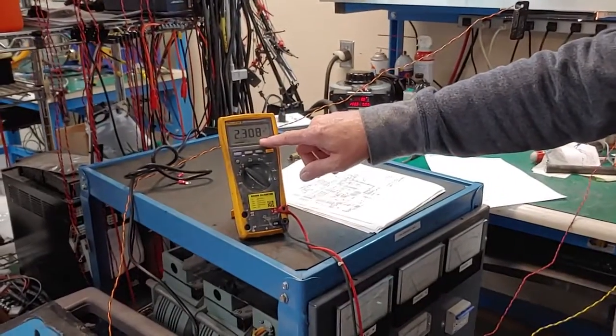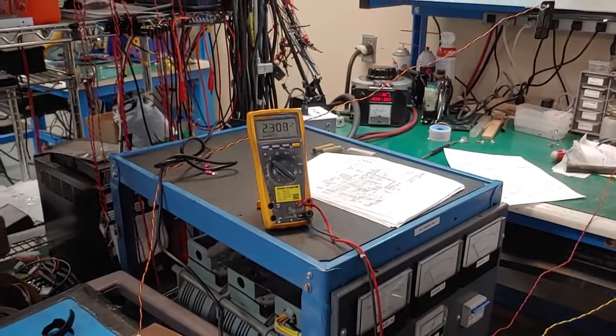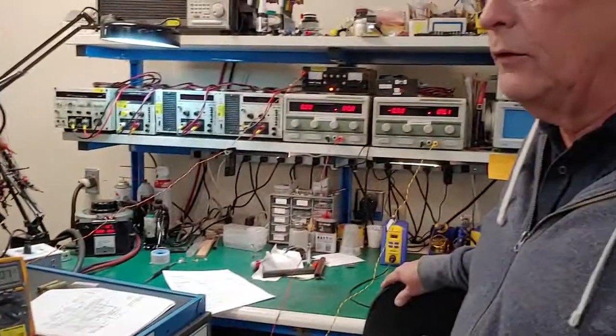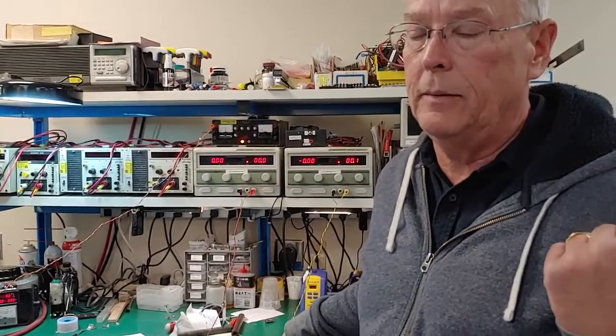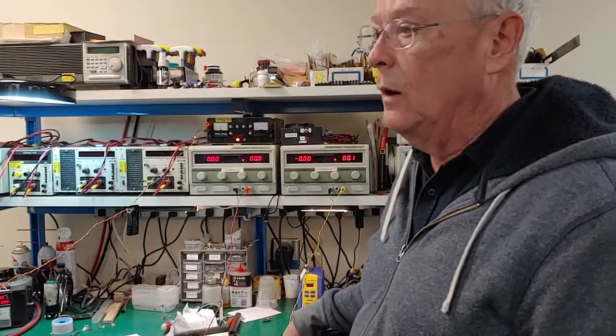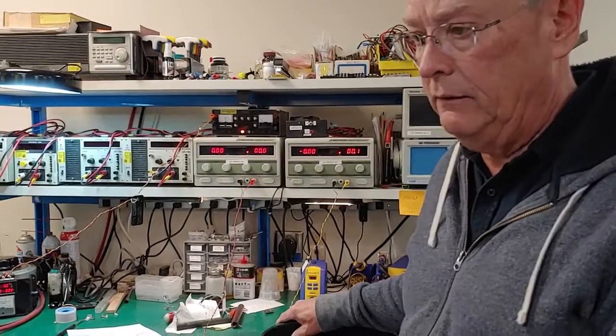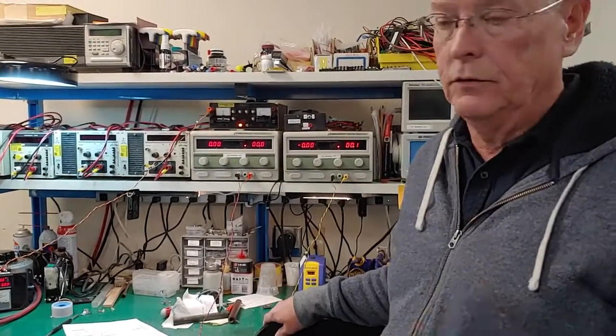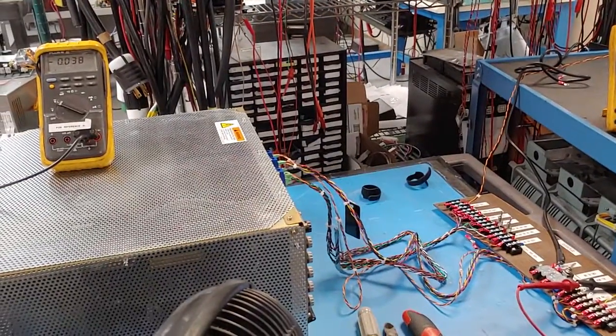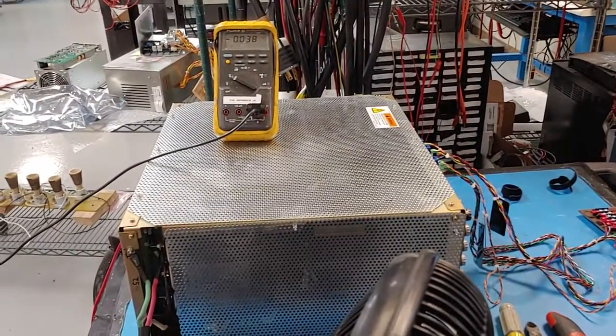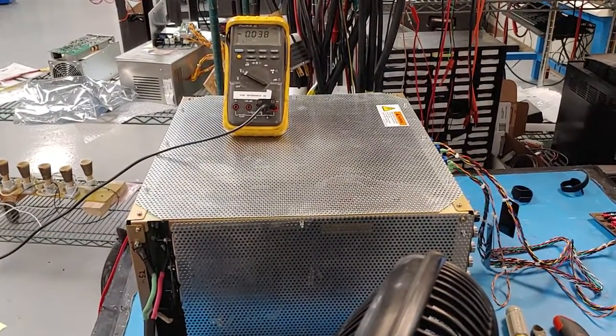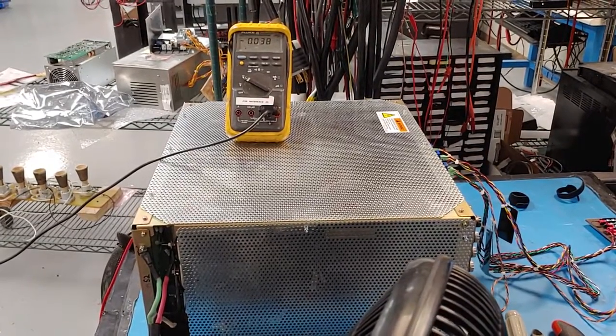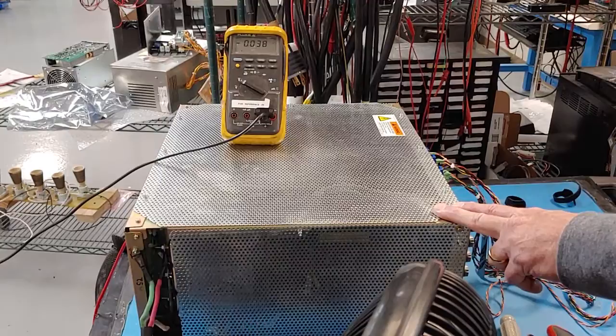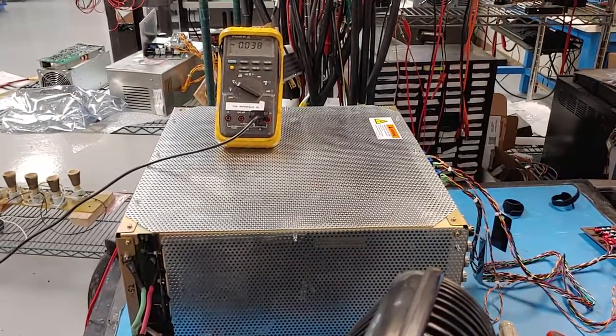We've got filaments now at 2.3. This is a standby filament. It allows them to warm up on this one without the high voltage being up. Like I said, the other one's different. The high voltage has to be up to about 15,000 before the filaments will come up. So it's by circuit design. Even though they're the same number, there's 2 different versions of circuits. So this one, by the way, is the one that was in your inventory as a spare, and we sent back fully repaired last time to you. And you said you installed this one to replace the original one that faulted, which is over there. So anyway, that's what this one is right now. We'll show you the other one here in a bit.